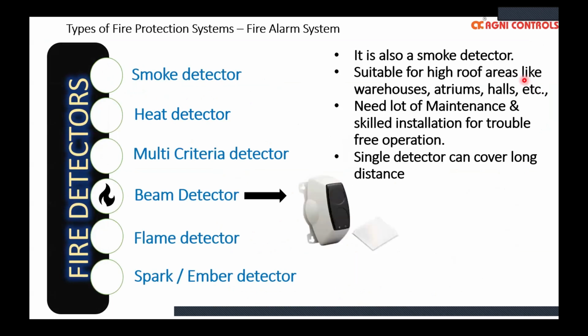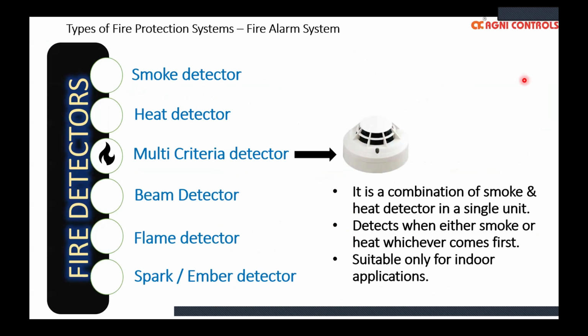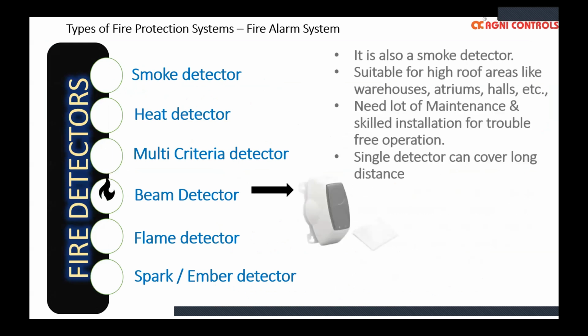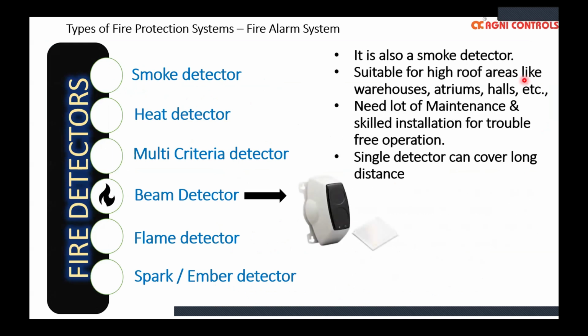Multi-criteria detectors are a combination of several sensing elements like smoke and heat. Nowadays, we also have IR and carbon monoxide, and other flame-related elements integrated into one single detector. And we also have the beam detector, which is also a type of smoke detector. It is suitable for high roof applications like warehouses, atriums, and very huge halls. The problem is that it needs lots of maintenance and a dust-free environment, and the alignment is a huge challenge during the installation phase. The advantage of this beam detector is that a single detector can cover a huge area.